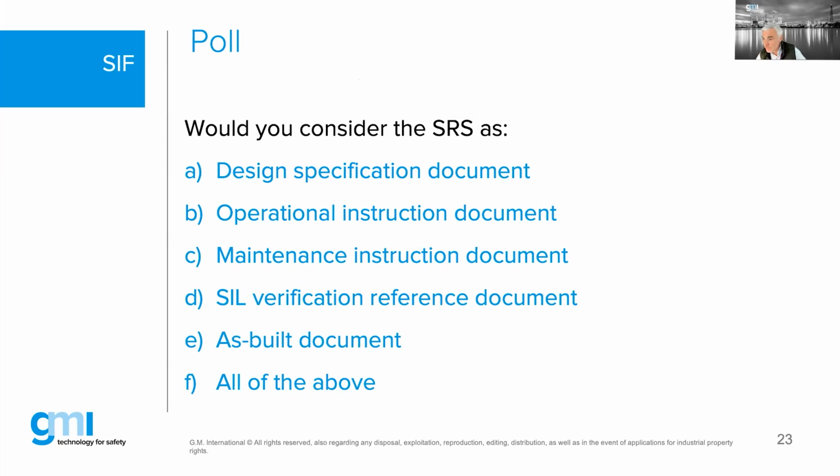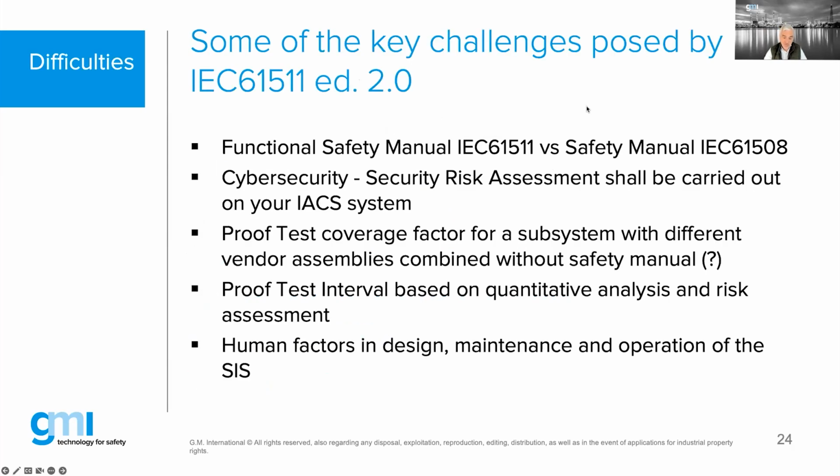Right, I got a very quick question coming in. How do you qualify the hardware and software taking the correct action? I would like to answer, if I understood the question better. That's a bit of a generic question. Requirements on the hardware depend on whether your project needs to be in compliance with IEC 61511. Then the first thing to look at is, what route selection have you decided? Have you gone for Route 2H? That means, have you gone for the famous prior use of your equipment, based on end user data? Based on that data, you can simplify and relax your architectural constraints into a certain design, if that is the specific question.